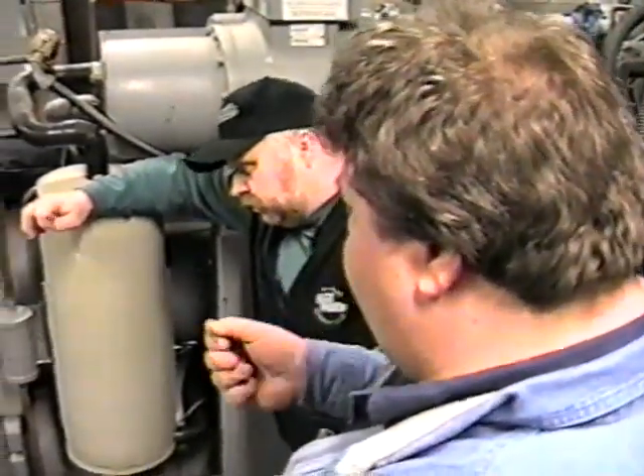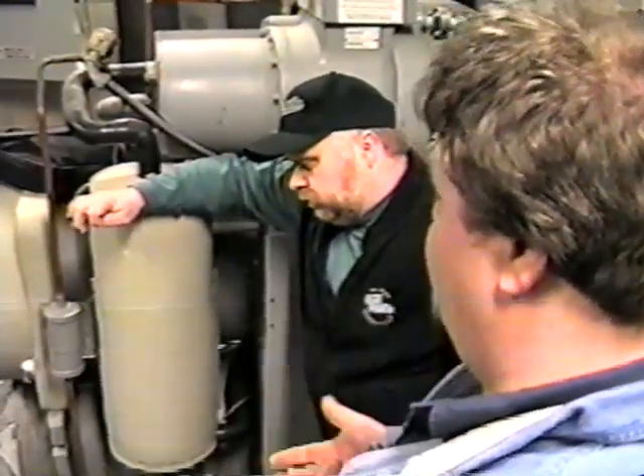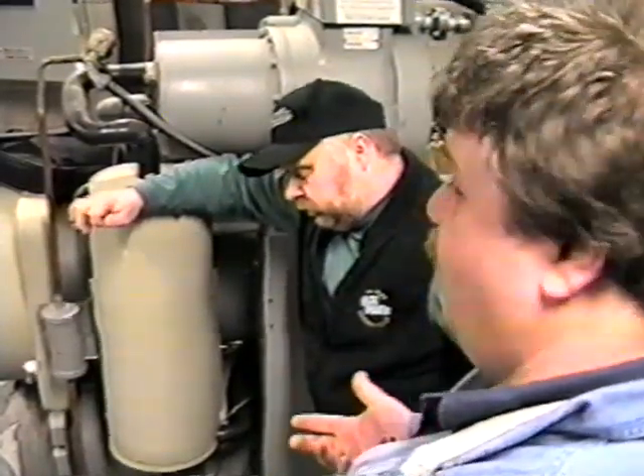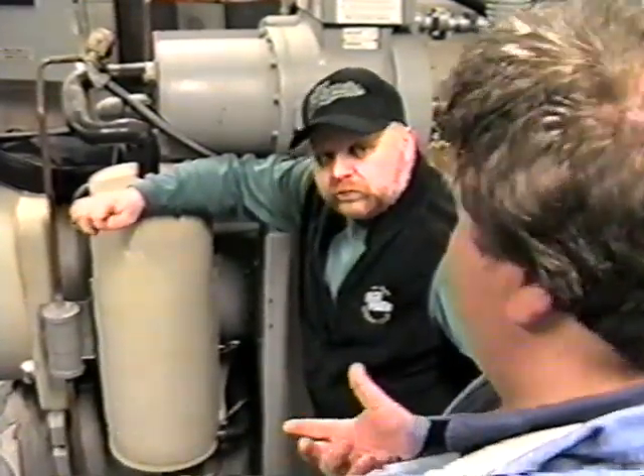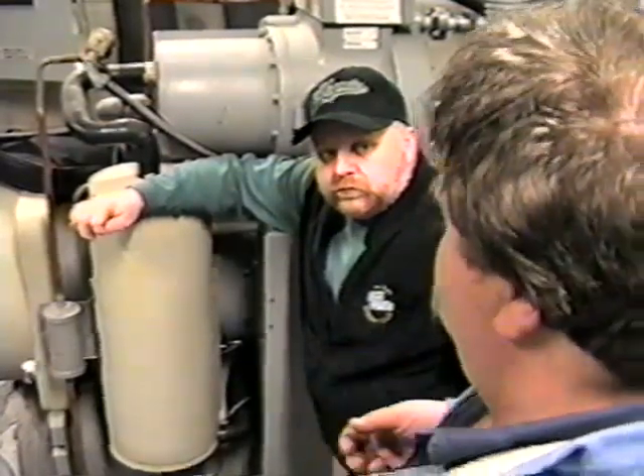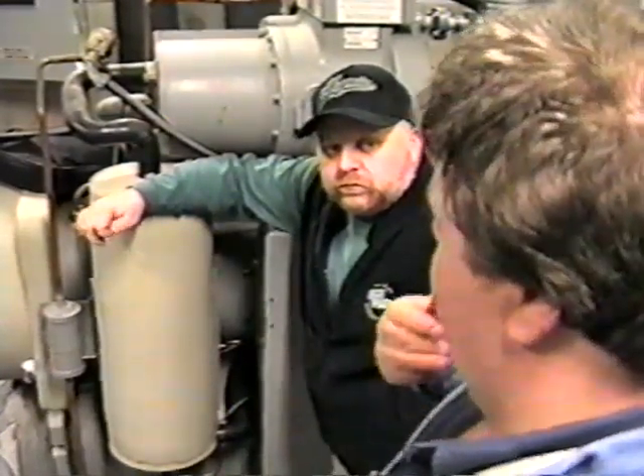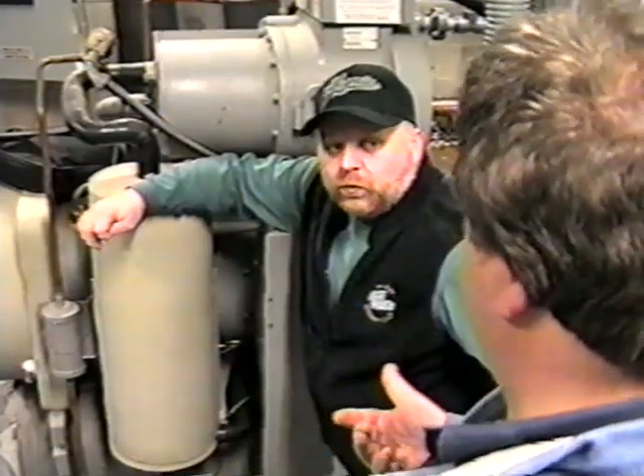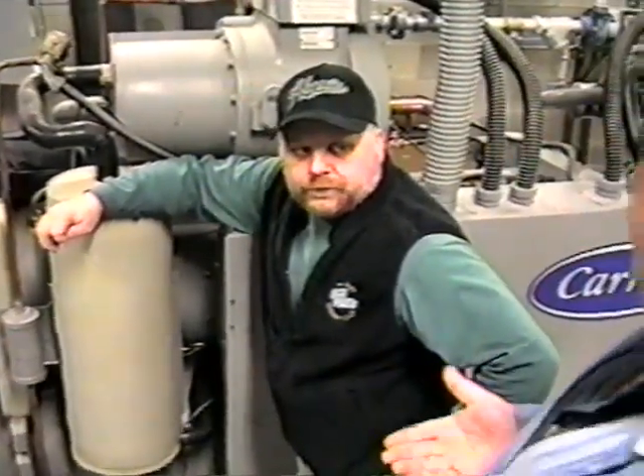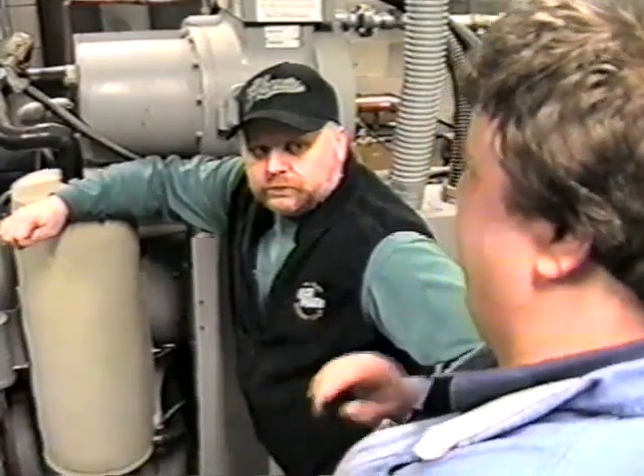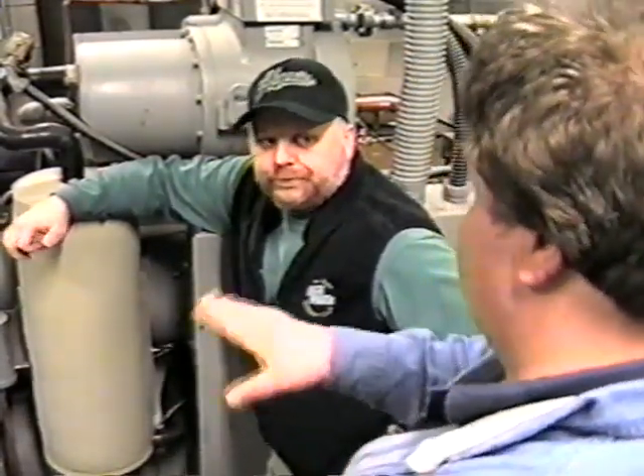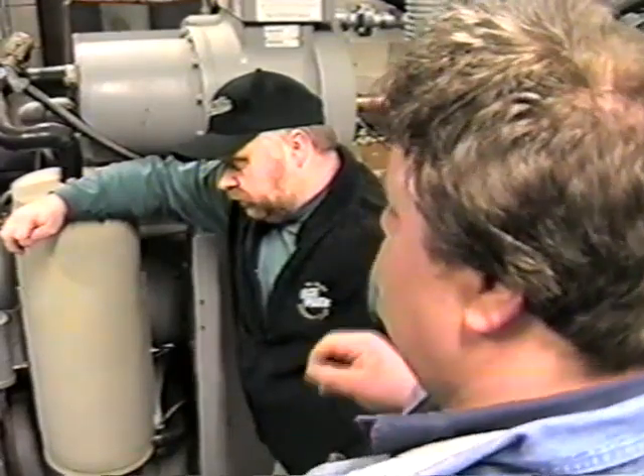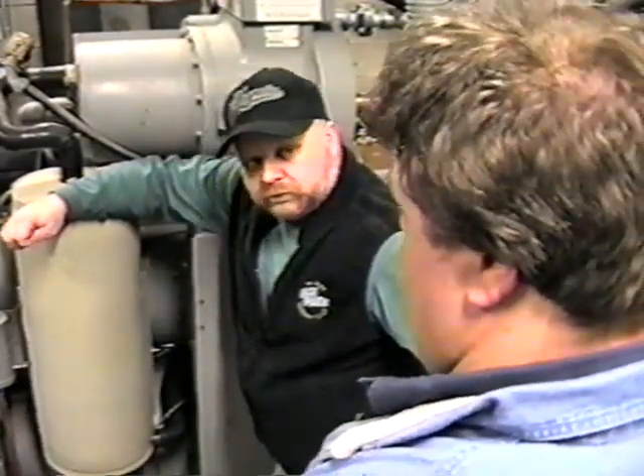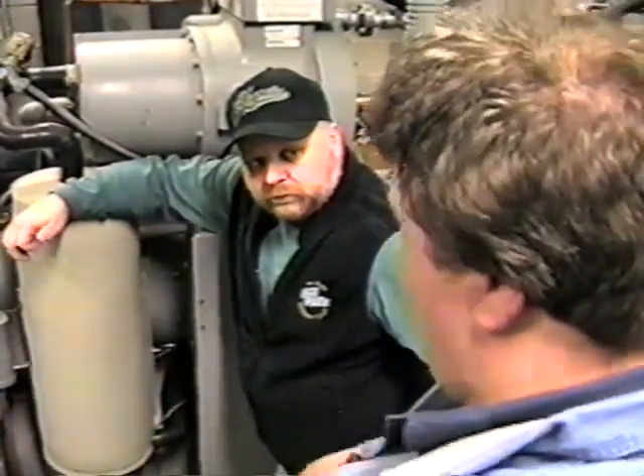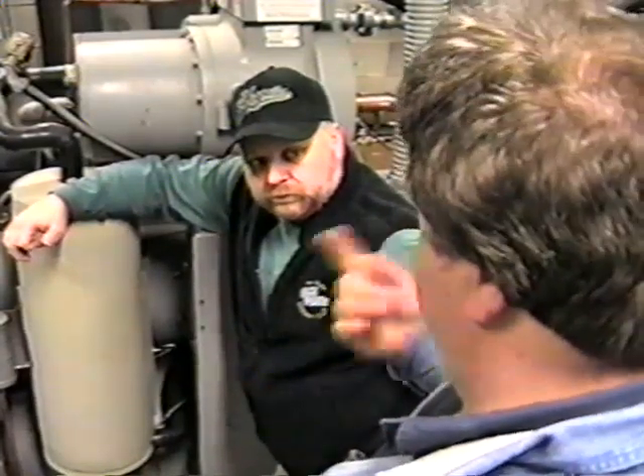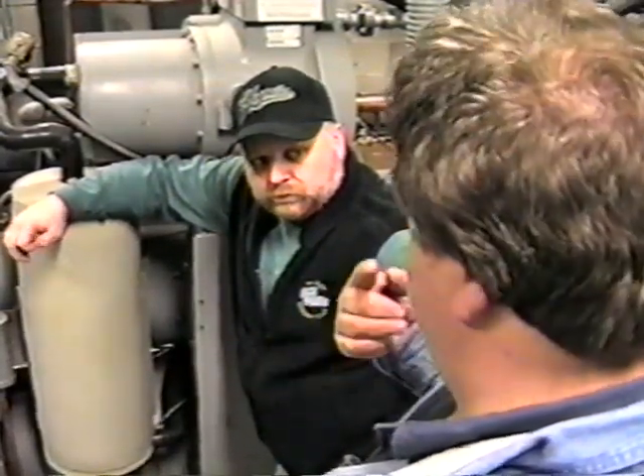Okay. Along with that, your sump also is the place where we get the underfloor heat. In lieu of using some other refrigerant to water heat exchanger, right, we're trying to do it a much safer way as far as not having leaks and stuff like that, right, and breaking into the system that's a package already. So all we've done is used a heat exchanger to take the sump water through that, and then on the other side of the heat exchanger is your underfloor loop system.